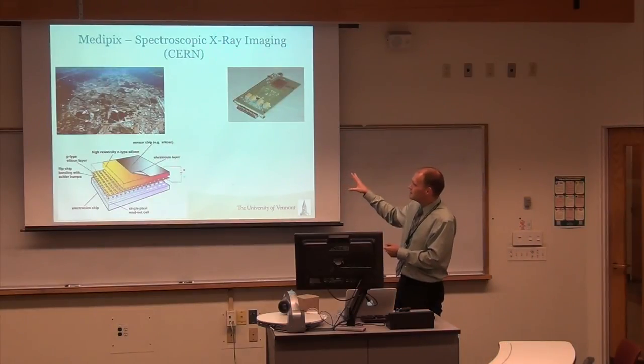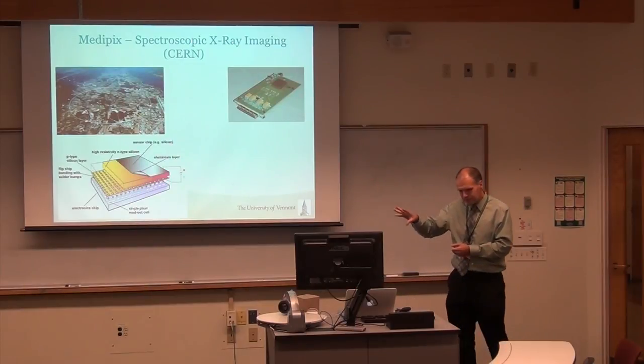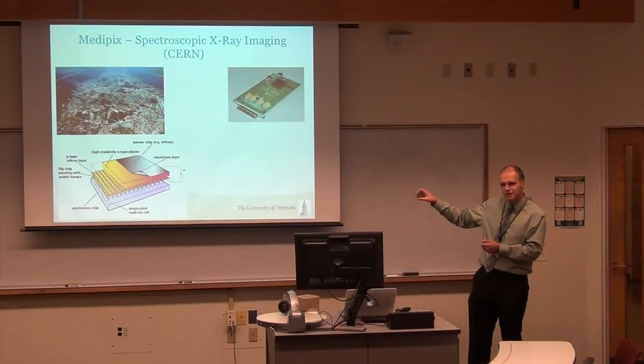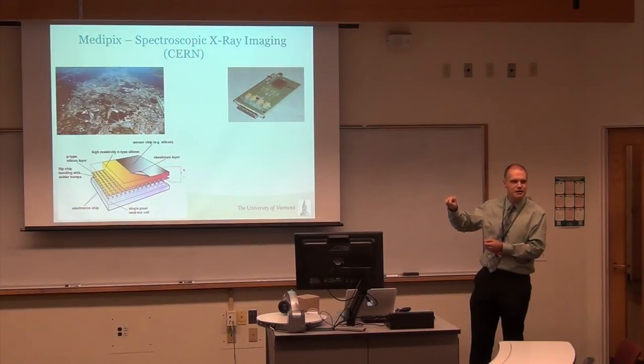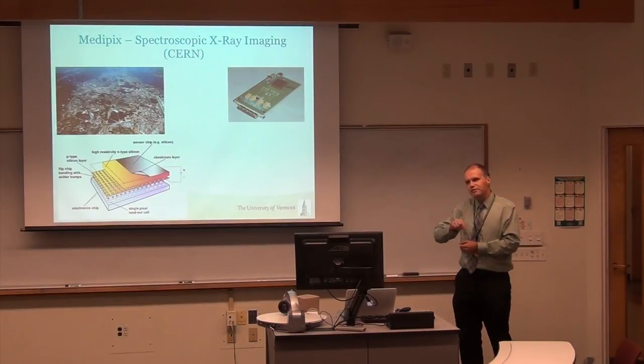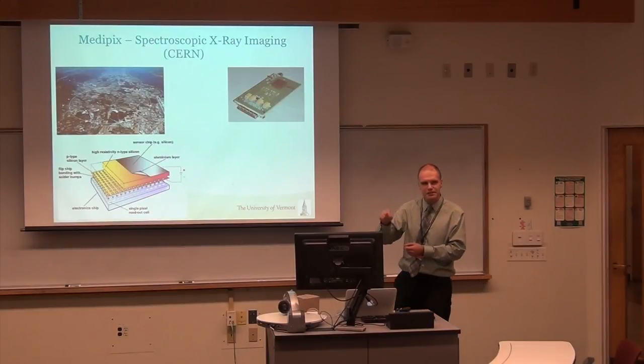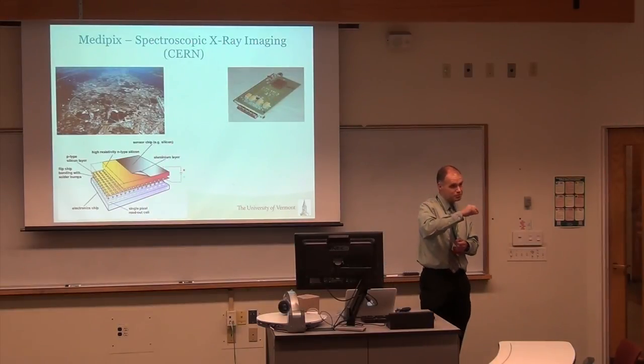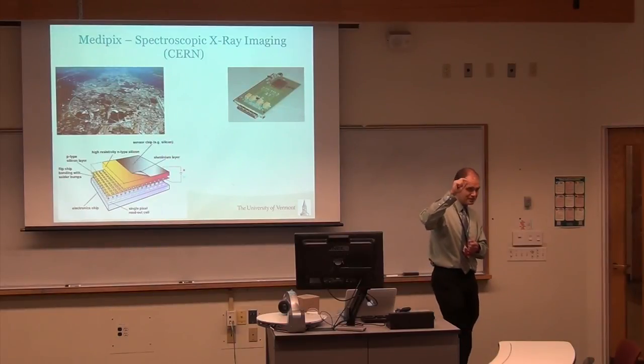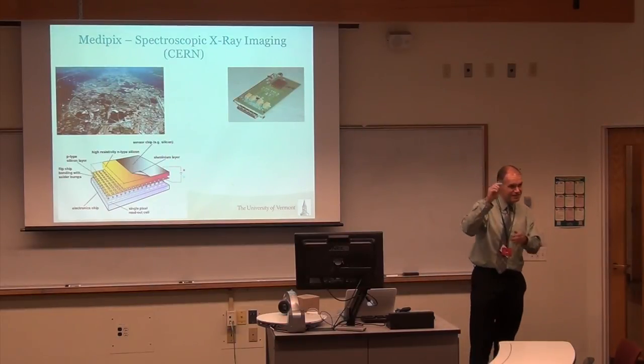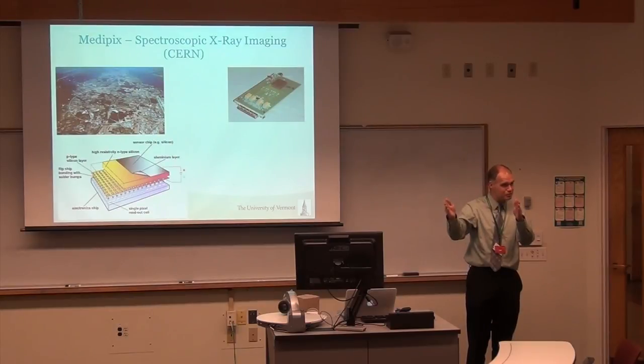What this detector tries to do is not just measure the total amount of charge, but it measures the energies of the individual photons hitting the detector. So if you look at a material, for example iodine, and look at its X-ray absorption, it has a very strong peak where you start hitting the k-edge of iodine.